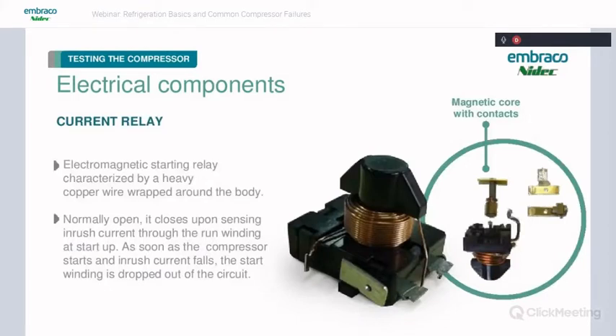That current relay is very common, and you can tell it's a current relay by looking at that heavy copper wire wrapped around the body. It's basically the coil of the relay. It's normally open, and how it works is it closes when the compressor starts and it senses the heavy inrush current through the run winding at startup. As this coil senses that inrush current, it's going to pull this plunger in and energize the contacts of the start winding. So, like I said, it's normally open.